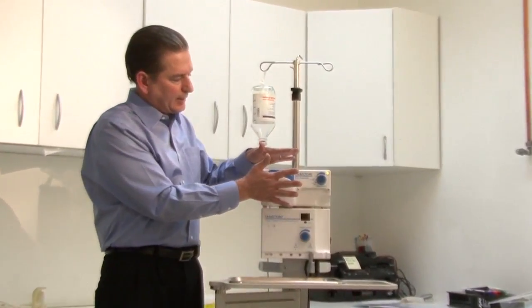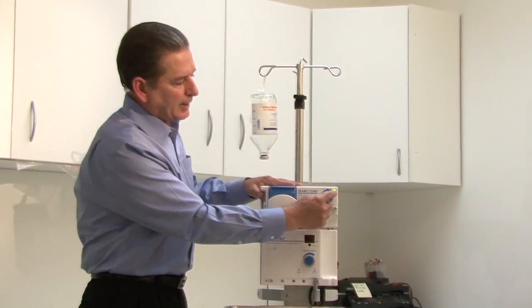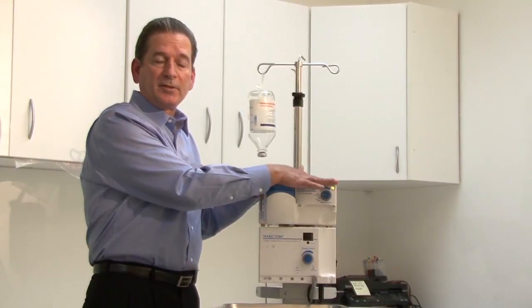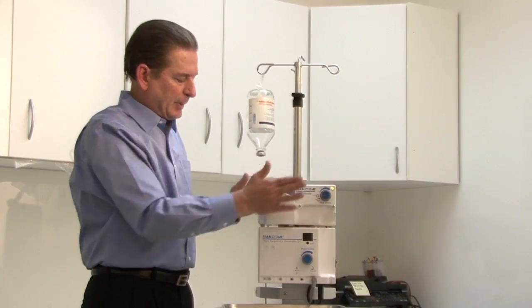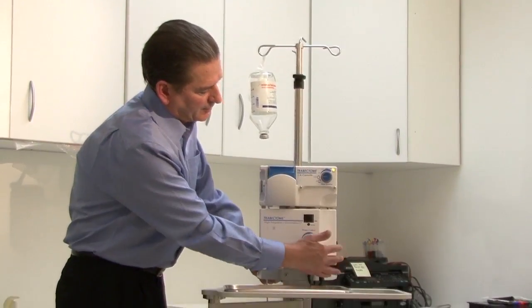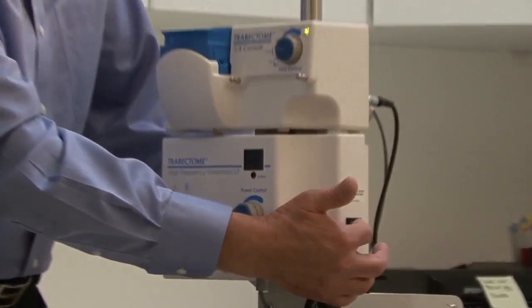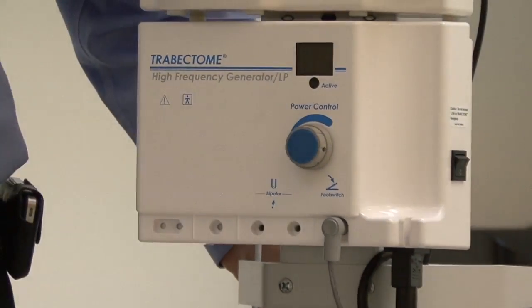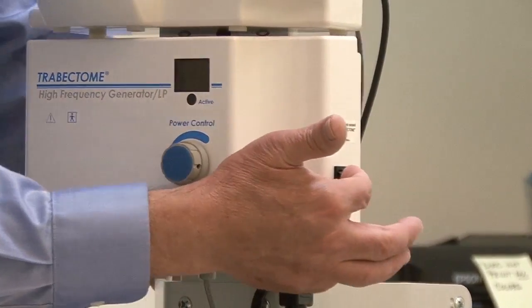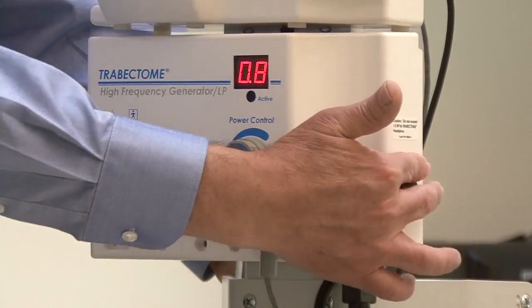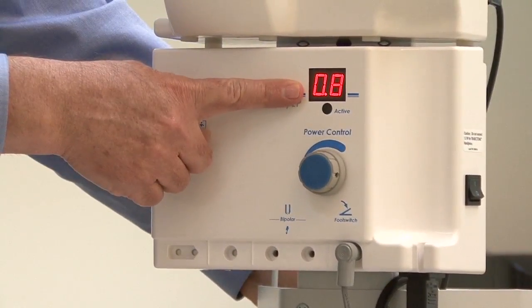Now when you plug in the irrigation aspiration pump, you'll see that the little power light comes on. It's ready to go. It's all powered up. But for safety reasons, the electrosurgical generator also has a power switch. So we want to make sure, in addition to plugging in the generator, that we go ahead and turn on the power here on the side, and we can tell that the power is on because the display lights up.